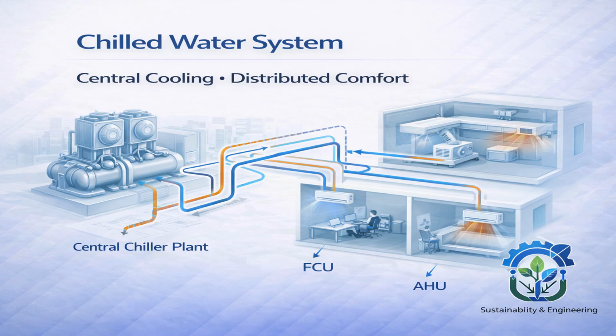So now let's move to a very important HVAC system, that is the chilled water system. This system works on a simple principle. Cooling is produced centrally and distributed locally. Instead of producing cooling inside each room, we generate chilled water at a central chiller plant. This chilled water is then pumped through piping to different areas of the building, where it is used by FCUs and AHUs to cool the spaces. That is why we call it central cooling with distributed comfort.